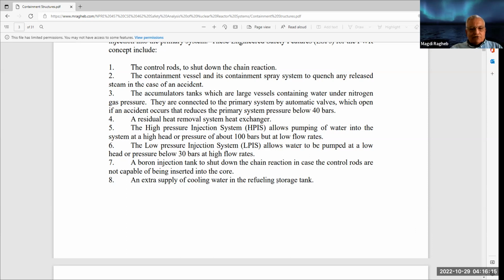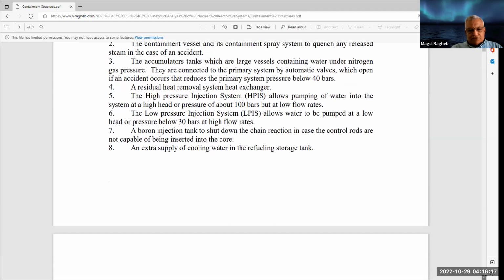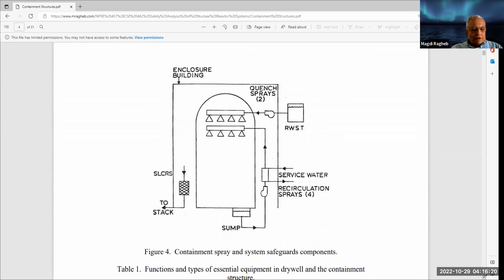And then an excess supply of water from the refueling water storage tank is available for the cooling of the containment. Most containments for PWRs and BWRs contain a spray system. You could see here, this is the steel structure. Now, we are not even showing here the concrete structure. People think, oh, the concrete structure is going to contain radioactivity releases in an accident. No way. You could see here that there is a provision of a containment spray. It sprays water, getting water from the RWST. This is what I mentioned a few seconds ago, the refueling water storage tank.